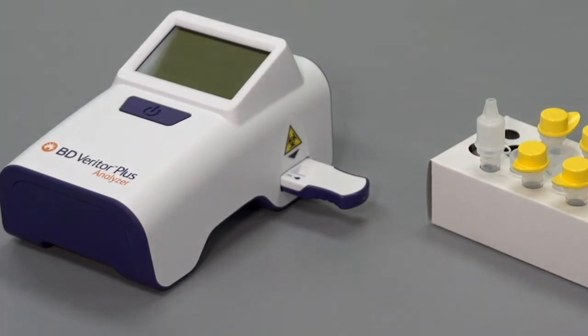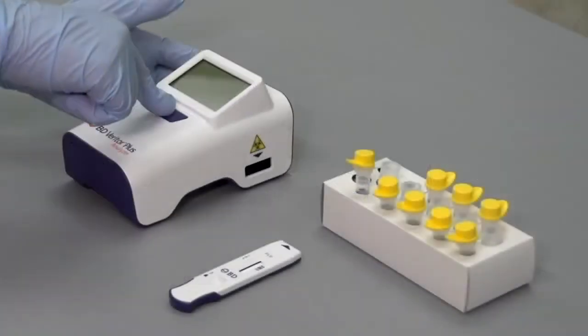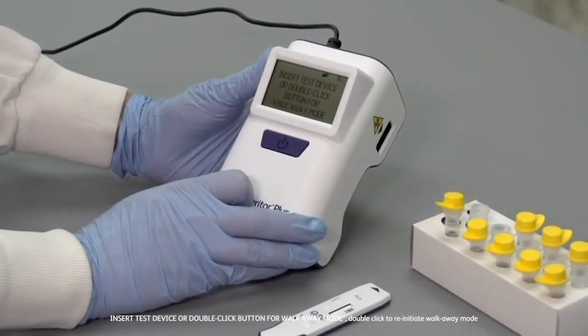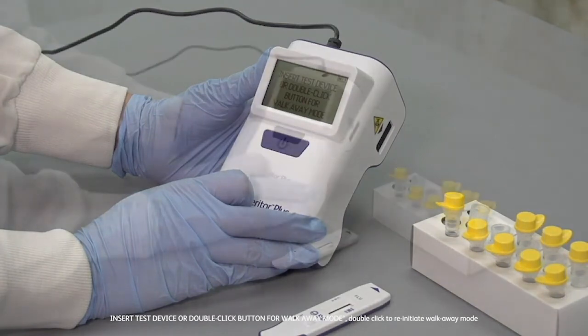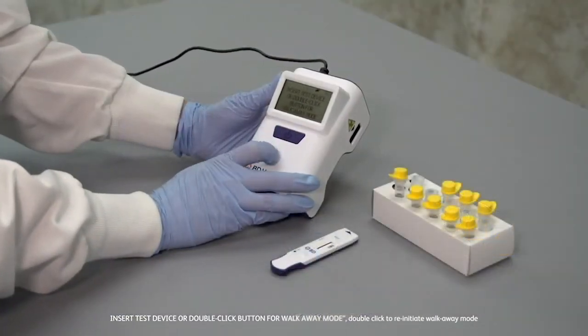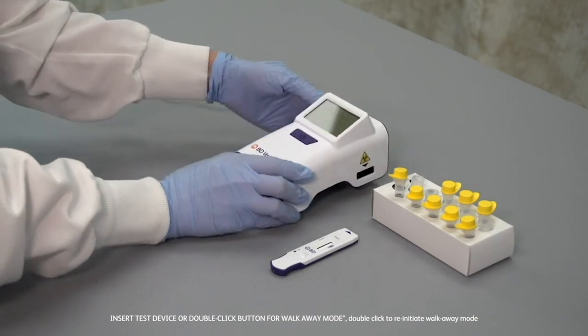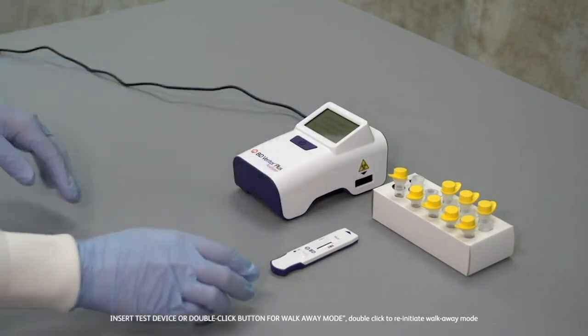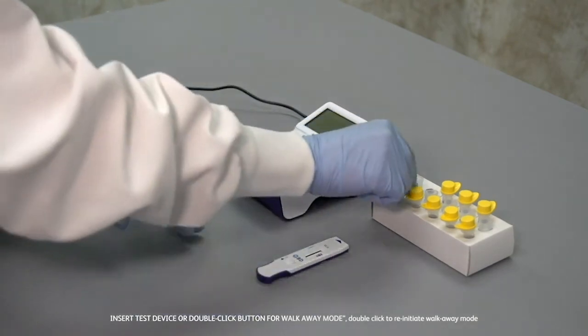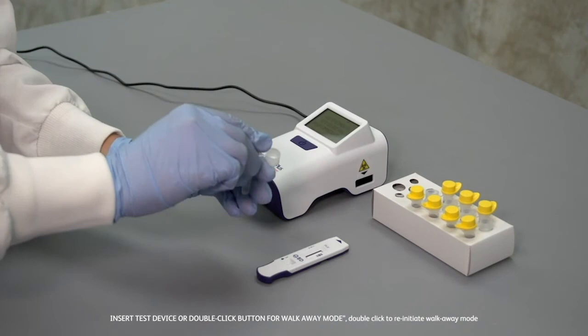Now we'll do a simulated walk-away test. Power on the analyzer. When "Insert Test Device or double-click button for walk-away mode" appears in the display window, double-click the power button. You'll be reminded to connect the external power if the analyzer is not already plugged in. This is a requirement for walk-away mode. Make sure the instrument is resting on a level surface.